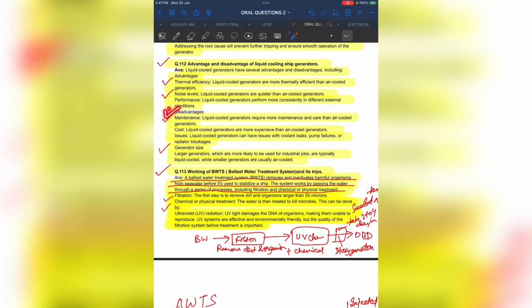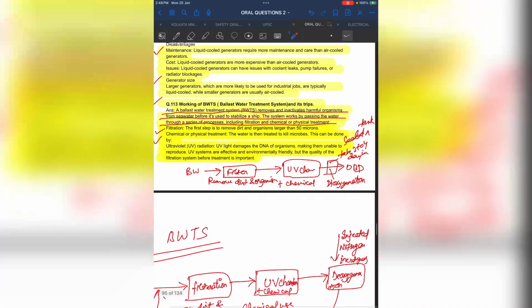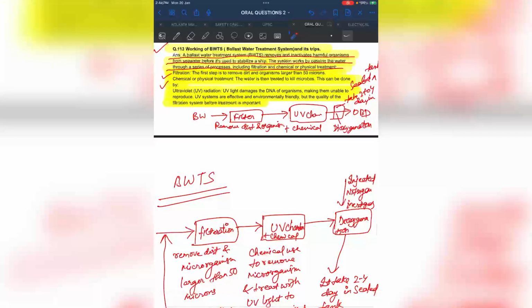And what are the disadvantages? Heavy maintenance: liquid cooled generators require more maintenance and care than air cooled generators. Cost is also high, as they are more costly than air cooled generators. The common issues in a liquid cooled generator are coolant leakage, pump failure and radiator blockage. The size of a liquid cooled generator is also larger than an air cooled generator. Okay, let's move to another question.